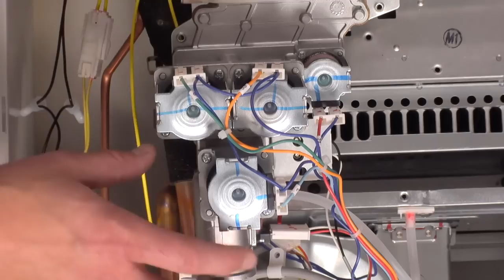Now flip it over, and you'll see all of your solenoid valves. There's actually 5 of them: a main solenoid valve, a modulating one, and 3 chambers here. Each one of these connections is unique to the solenoid valve, so we've got to keep those straight when we put them back on.